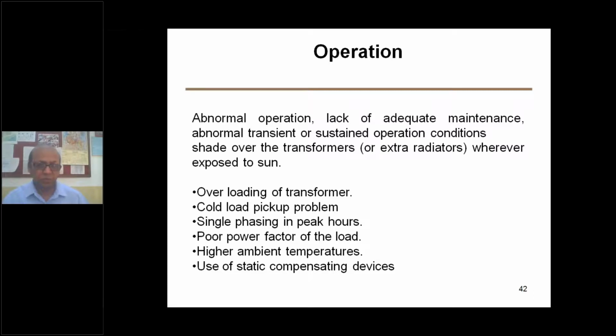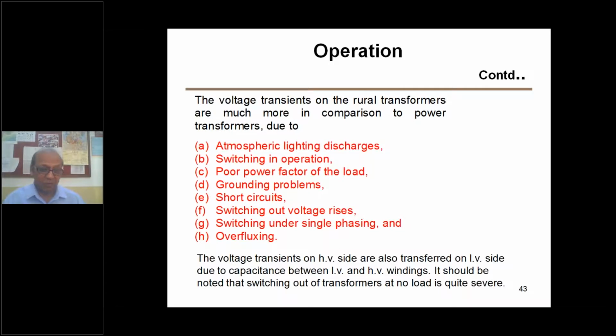Poor power factor is another problem. Higher ambient temperatures may cause higher temperature rise of the transformer and failure of the transformer. Use of static compensating devices — meaning computers and various electronic devices used in houses and industry — also brings in a lot of harmonics. That is another kind of problem affecting distribution transformers, and it is also looked into depending on the locality.